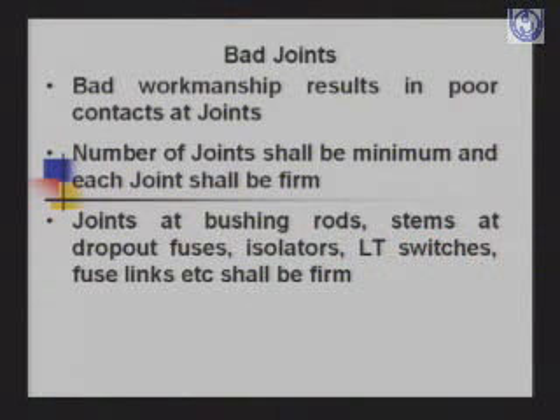When we come to improvements in joints, bad workmanship results in poor contacts at joints, which results in higher losses. So the number of joints should be minimum and each joint should be firm. Joints at bushing rods, stems, at dropout fuses, isolators, LT switches, fuse links, everywhere you should take care of joints. In fact, in a World Bank study conducted at Haryana, it was found that the losses due to bad joints alone were around 3 to 4% of the total loss. And this loss is not being considered anywhere in our system. We don't count this towards loss.